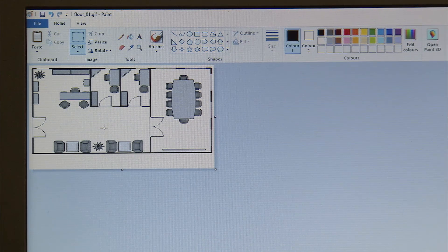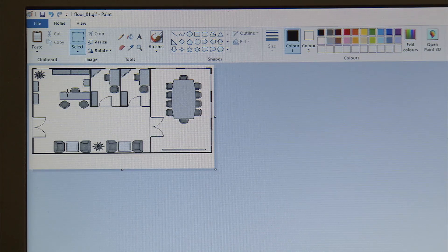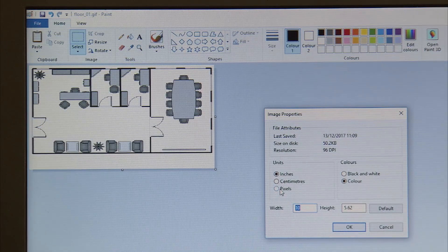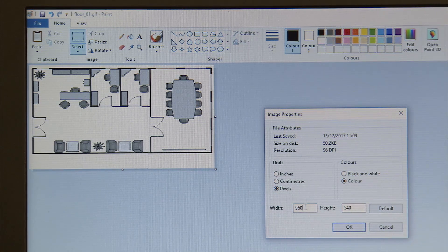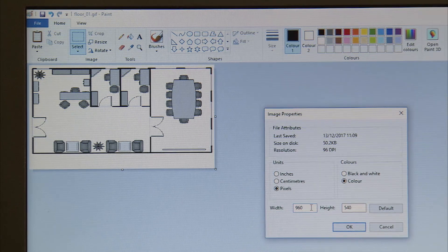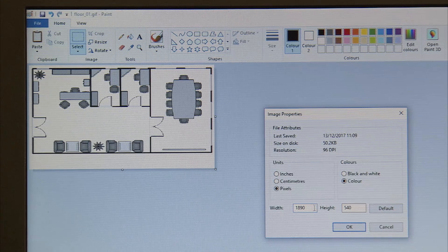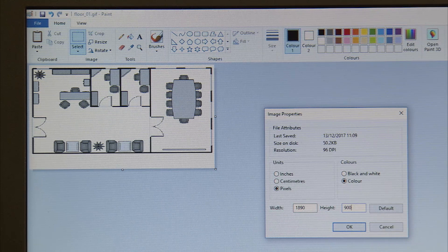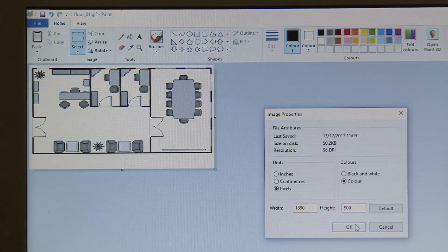Creating a floor layout on the computer to upload onto the centralized controller. First, we need to make sure the screen relates to the screen on the actual centralized controller. We specify pixels, which relates to dots. We need a width of 1890 and a height of 900, which relates to the number of pixels or dots on your centralized controller.